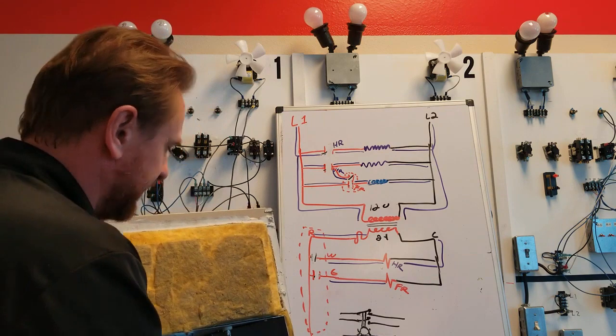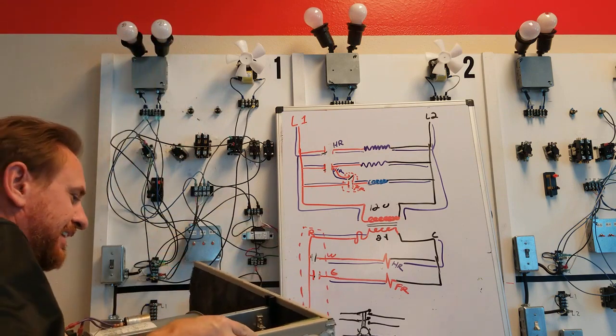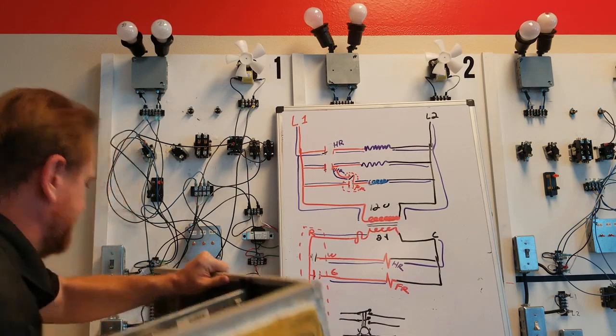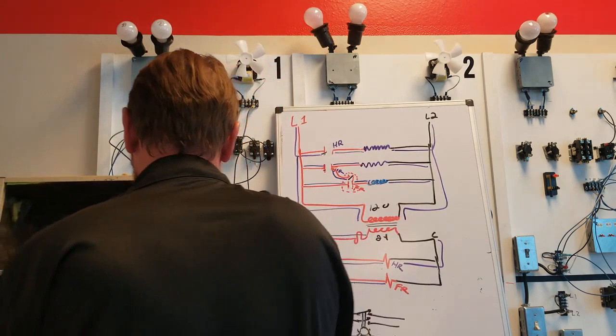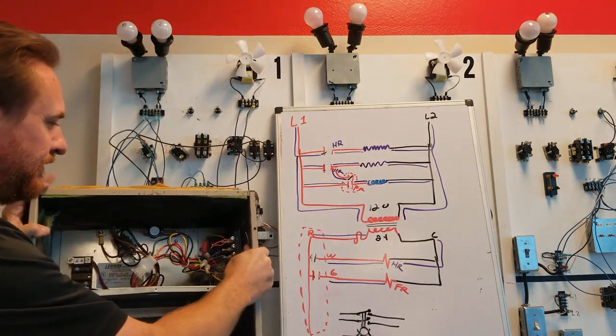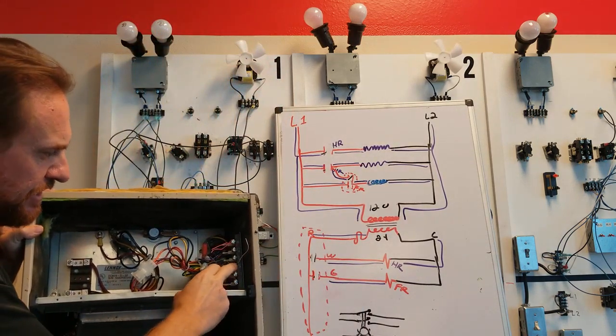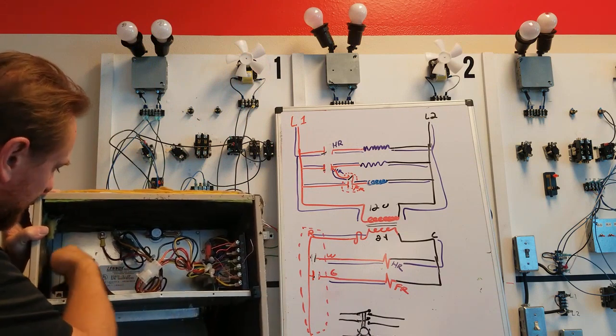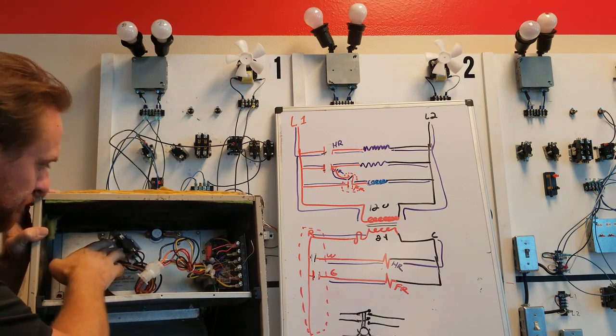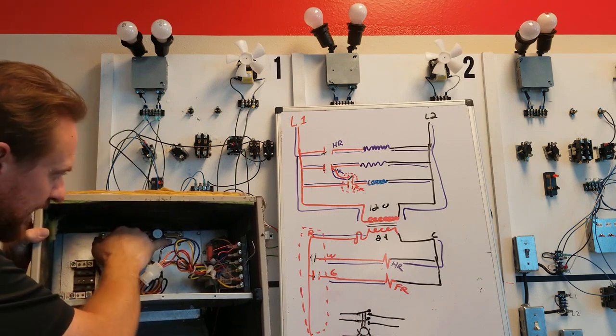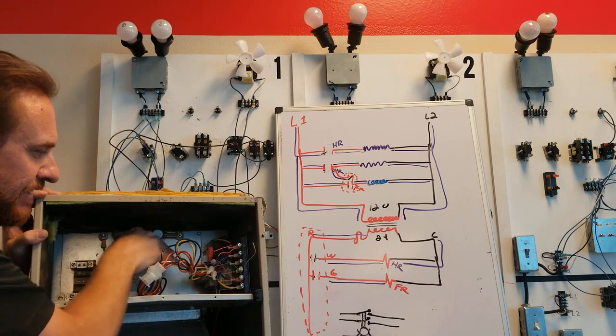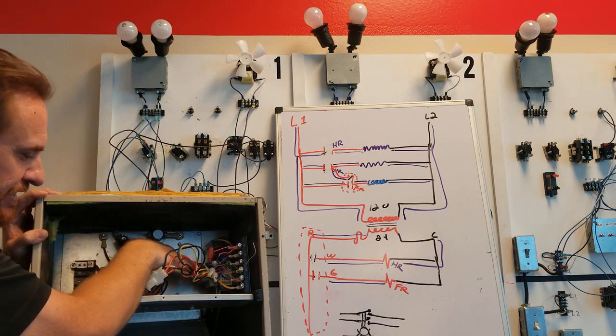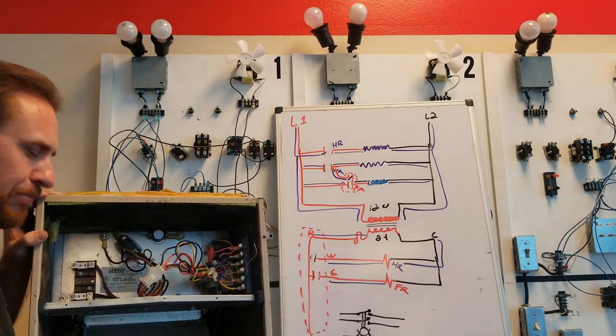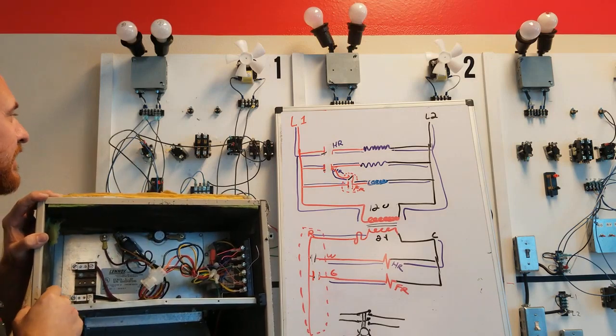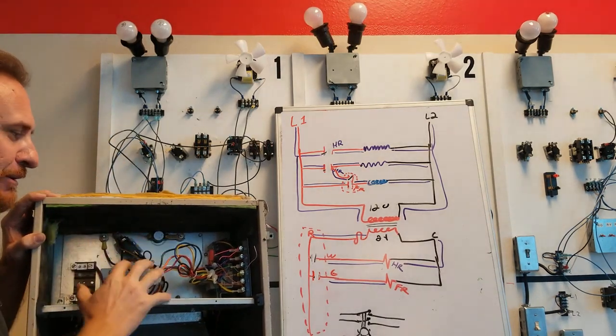Just a coil of wire, resistive elements. But if we look inside, we have all of our same components. We have our letters, C, G, W, and R. We have our line 1 and line 2 that comes in. This one's using a sequencer. We have one heat element. We have our relay that controls our fan. We have our transformer, takes it from high voltage down to low voltage. We have our blower motor. So it's just like the system we have here, except it's just a little bit more compact.